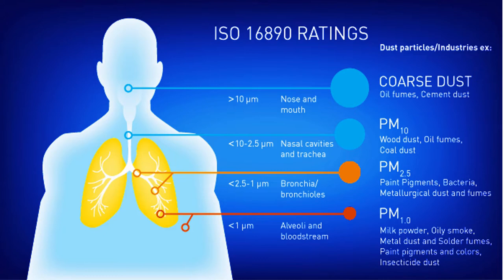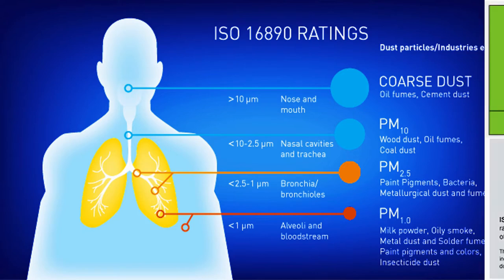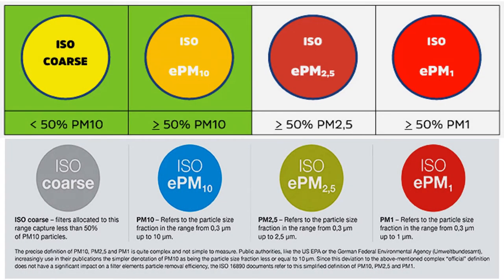The new ISO 16890 standard divides air filters into 4 groups. A prerequisite for each group is that a filter captures at least 50% of the appropriate particle size range. If the filter captures more than 50% of PM1 particles, it will be grouped as an ISO ePM1 filter. The respective efficiency is then reported rounded in 5% increments. Alongside fine dust filters, the new ISO standard also evaluates coarse dust filters as ISO Coarse — that is, filters that capture less than 50% PM10.